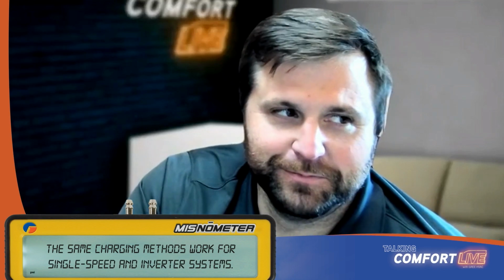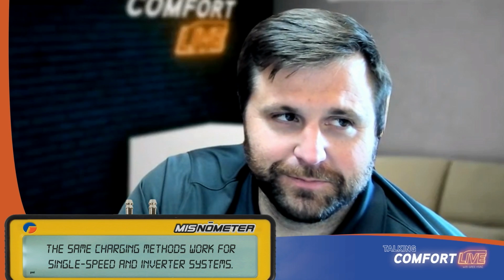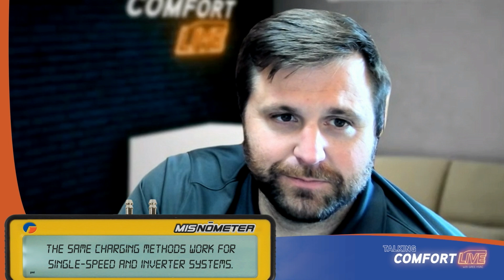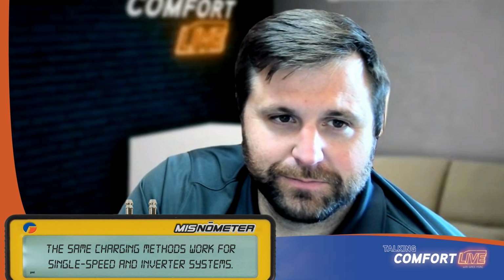So what are some of the differences that we might discuss between charging single speed versus inverter driven equipment? Well, realistically, whether you're talking single speed or 2-speed versus an inverter driven system, when you're talking single speed or 2-speed, you have a means or a method to lock that into second speed, or you only have the 1 speed. We have a truly inverter driven unit, such as the GREE units that we sell and support. These are fully variable systems. So in order to charge them properly, you would have to know, you'd have to have a way to lock them to a specified speed and then have the data behind it to be able to charge it adequately.